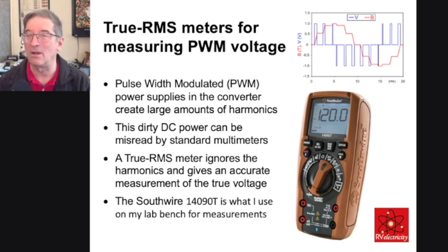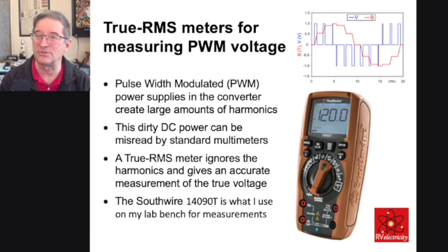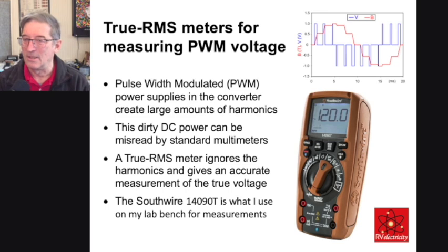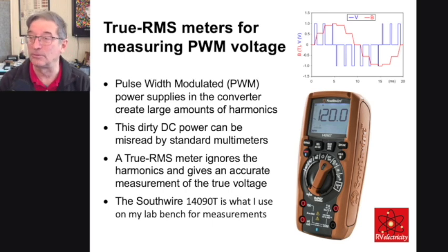You don't have pure DC, you don't have pure AC. You have something in all of these RVs called a pulse width modulated power supply. You can see my little diagram at the top there—it just makes a bunch of high frequency harmonics. This dirty power can fool a lot of meters. So if you have a standard meter measuring really weird stuff super high, it's probably because you're on a pulse width modulated power supply.